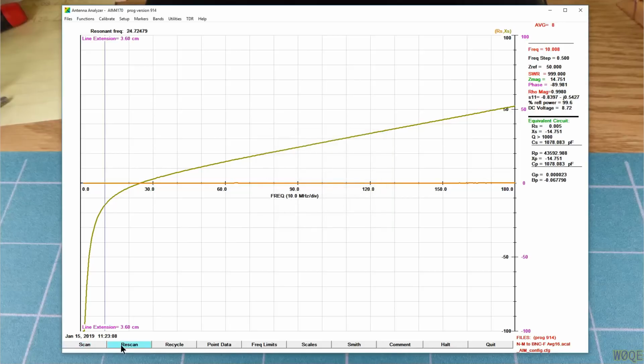And I can rescan this. I'll leave this scan on the chart, and I'll rescan it. And what we're seeing now is something that's a lot better. Before, it went inductive at 24 megahertz. Now it appears to asymptotically approach zero, which is what you would expect a capacitor to do as it goes up high in frequency. The effective capacitance we see is around 900 picofarads. At 10 megahertz, it's still 903 picofarads. So it's a much better circuit. This is more attuned to what the capacitor really looks like.